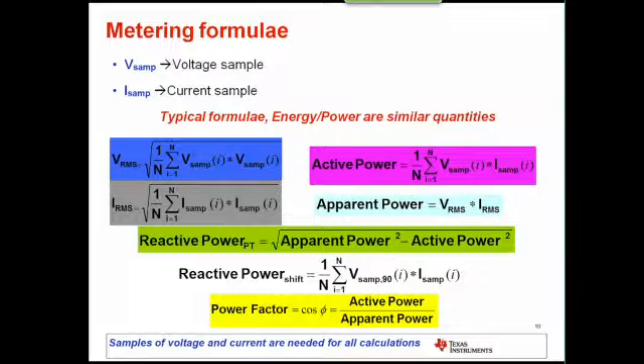So this slide shows how the various mean parameters are calculated. For root mean square voltage, you basically take each individual voltage sample, square it, accumulate it over time, take the average, and then take the square root. Similarly, for root mean square current, you do the same thing except with current samples instead of voltage samples. To calculate the average active power, you take each voltage and current sample, multiply them together, accumulate it, and take the average. For the apparent power, you multiply the root mean square voltage by the root mean square current.